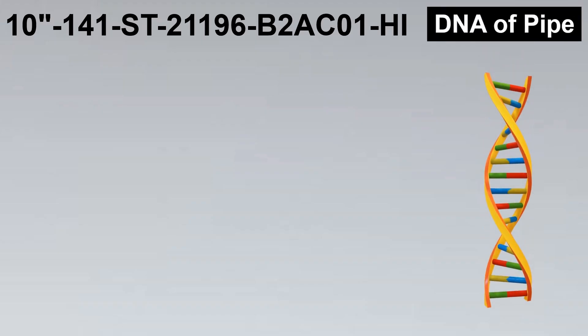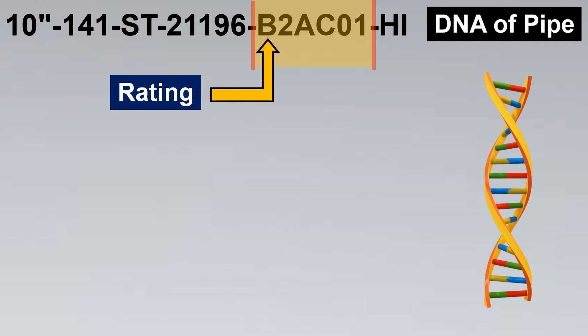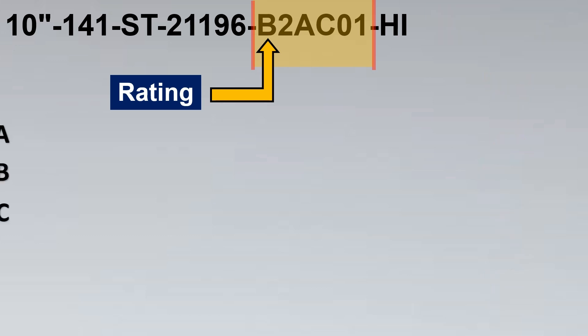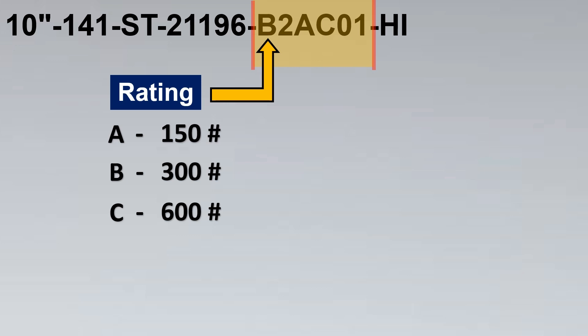So here's our line number mentioned and this is the DNA of the pipe. Let us try to decode the DNA of the pipe. The first thing is the rating. Now if you see here in terms of the rating these alphabets represent, for example A represents 150 rating. B represents 300. C represents 600. D might represent 900 and so on. So this alphabet, first alphabet, usually is used to represent the rating.